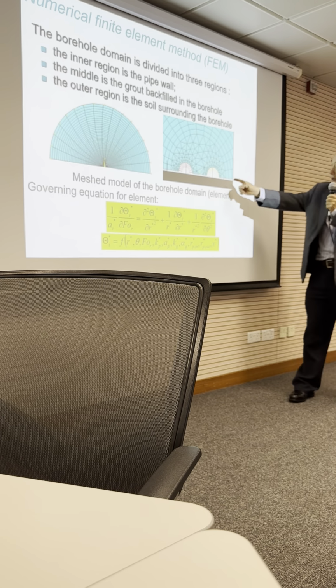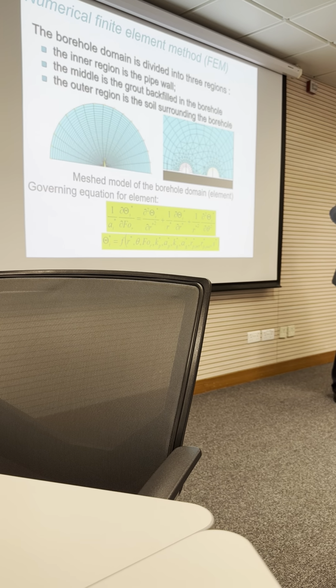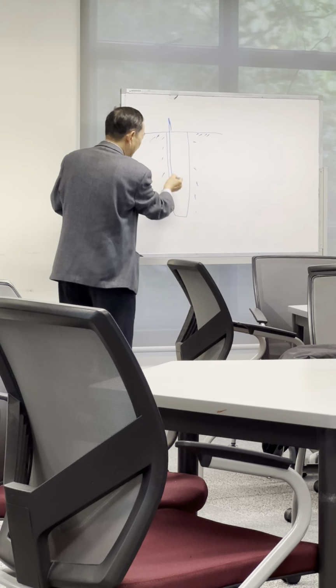We must consider the heat transfer from the water in the pipeline to the surrounding in the borehole. Inside is not water surrounding the pipeline. The pipeline is only 3 or 4 centimeter diameter. Then surrounding the pipeline, we call it grout backfill, as shown. You see, if this is the ground, and then we drill boreholes, then this is the ground, soil. Then we put one U-tube pipeline.